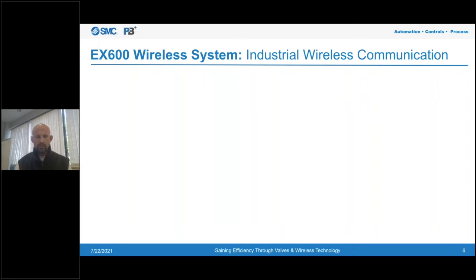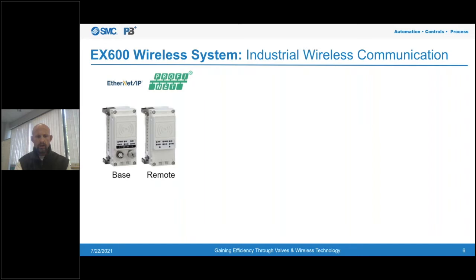So we developed a wireless technology where we can have valve banks and I/O blocks attached directly to the robot arm without a communication wire back to the PLC, but instead a wireless communication option, so those units can communicate wirelessly back to the PLC. This is really the genesis and basic concept behind our EX600 wireless system.